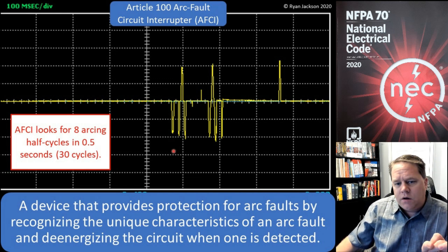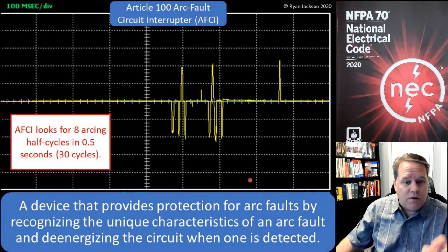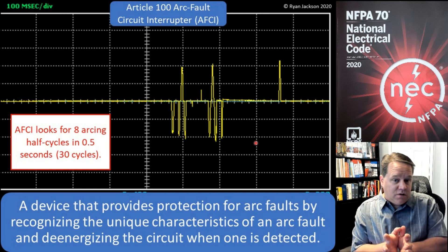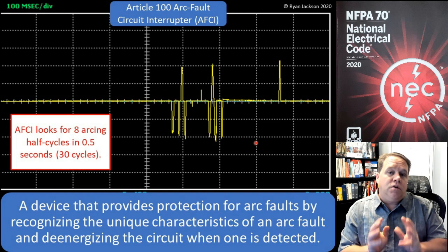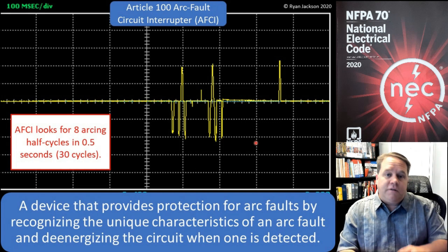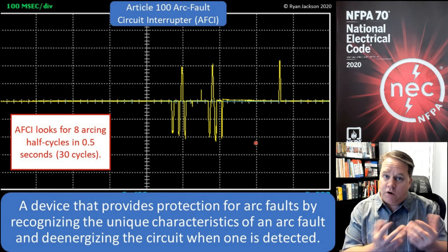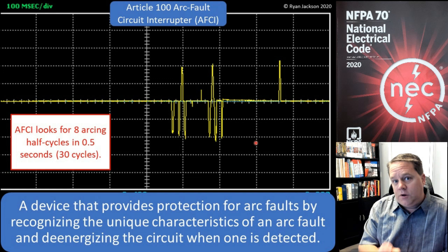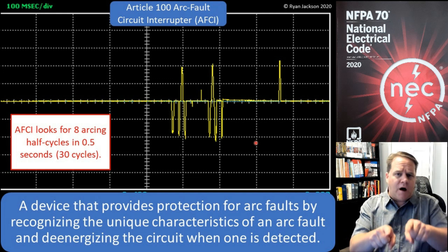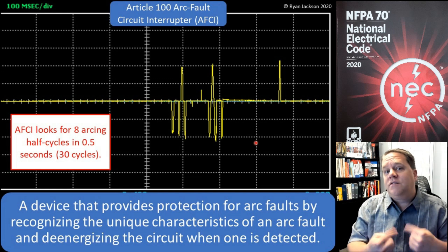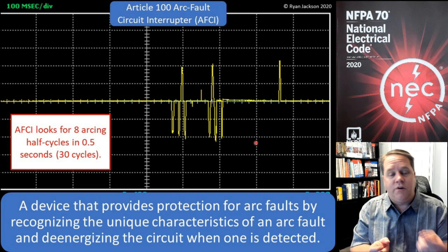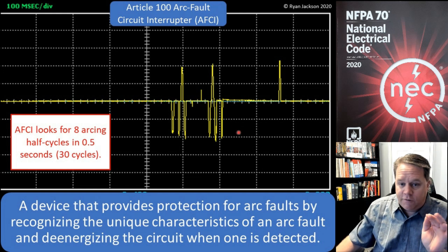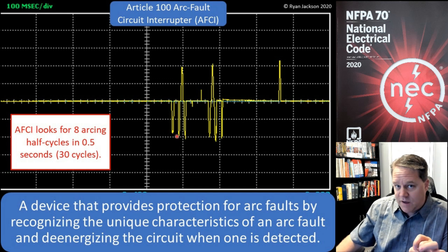An arc fault circuit interrupter counts how many of these peaks happen. What it's looking for is eight arcing half-cycles in 30 cycles — so in half of a second, if we see eight of those happen, we know that is a dangerous arcing fault. But it's only dangerous if it exceeds a certain amount of current. If there's essentially no current flowing, there's no danger. For a parallel arc — hot to neutral — we're looking for a 75-amp arc that happens eight times in one half of a second.